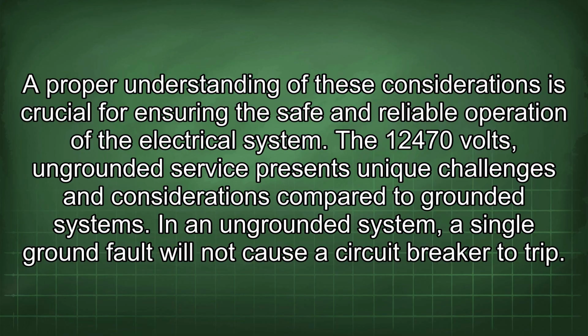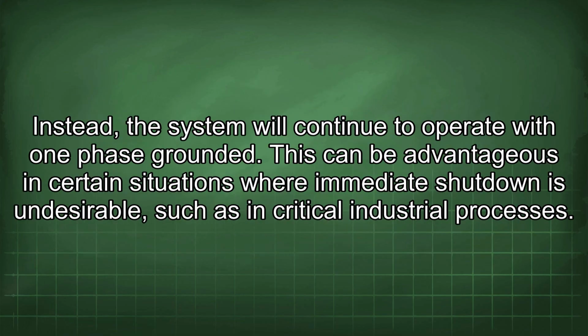The 12,470 volts ungrounded service presents unique challenges and considerations compared to grounded systems. In an ungrounded system, a single ground fault will not cause the circuit breaker to trip. Instead, the system will continue to operate with one phase grounded. This can be advantageous in certain situations where immediate shutdown is undesirable, such as in critical industrial processes.